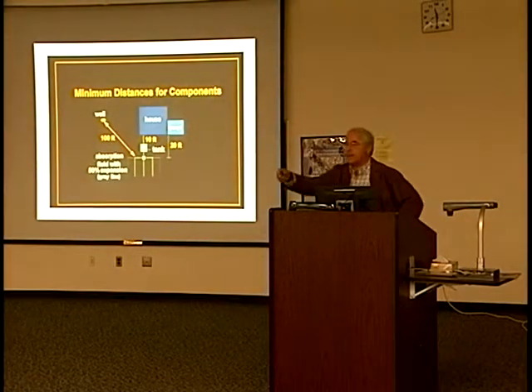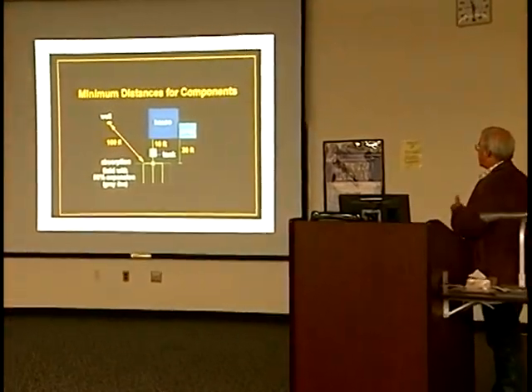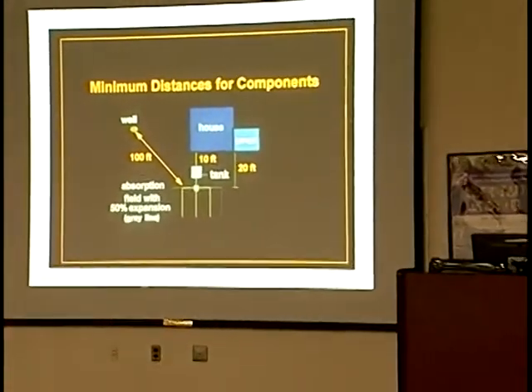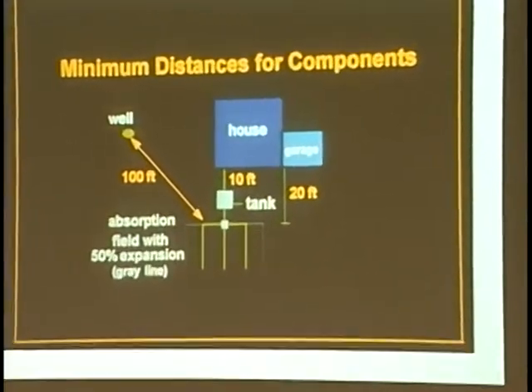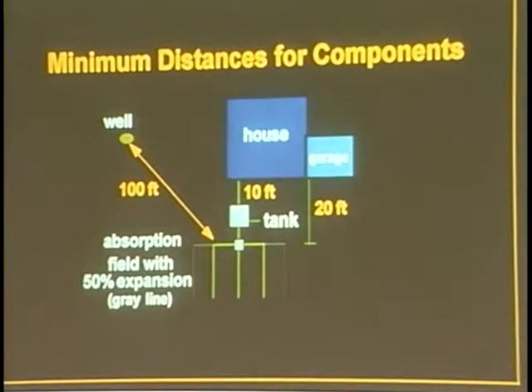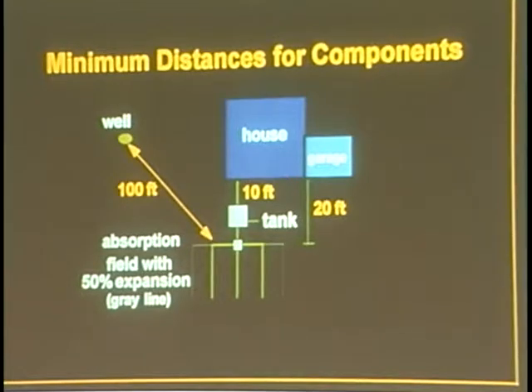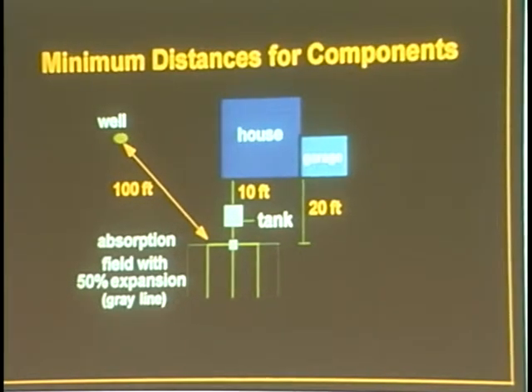Other requirements in Appendix 75A include your lateral dimensions. You've got to be so many feet away from the house — 10 feet from the tank, 20 feet from the leach field, 10 feet to a property line, and 100 feet from a body of water. Your leach system is supposed to be 100 feet from a body of water, 100 feet from a well water supply — not only your well, but 100 feet away from your neighbor's well to prevent your system from contaminating it.